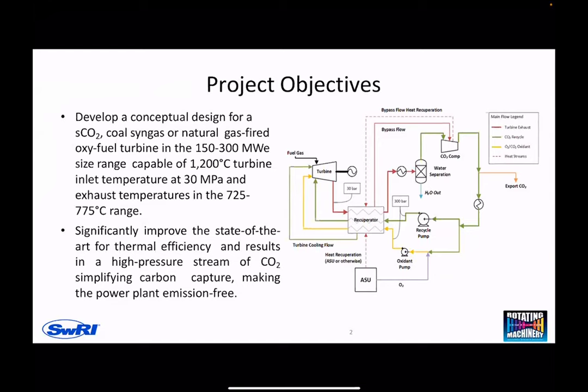In terms of limitations, the indirect fired cycles are limited based on material temperatures on the heater upstream of the turbine. These direct fired cycles are limited by the temperature downstream of the turbine due to internal recuperation. There's a lot of development going on in high temperature recuperators, but right now exhaust temperatures are in the 725 to 775 C range.